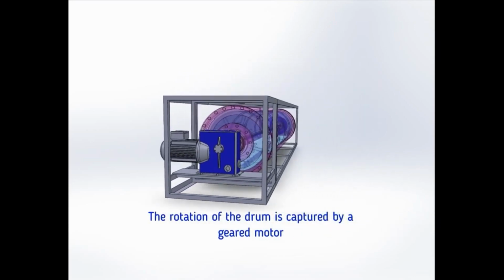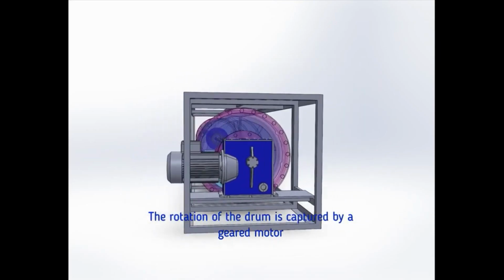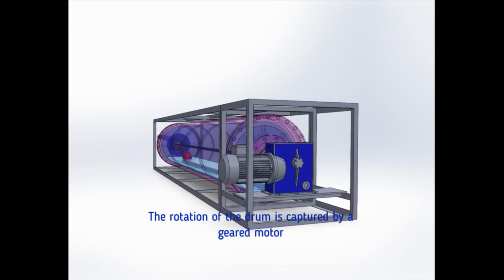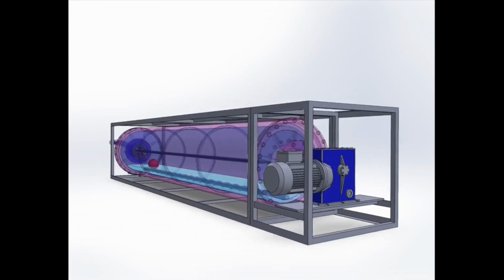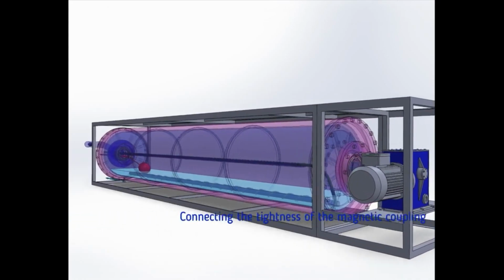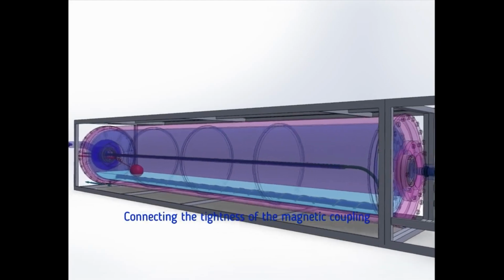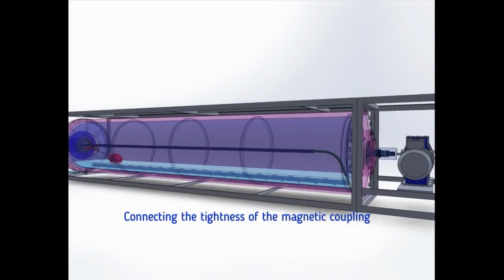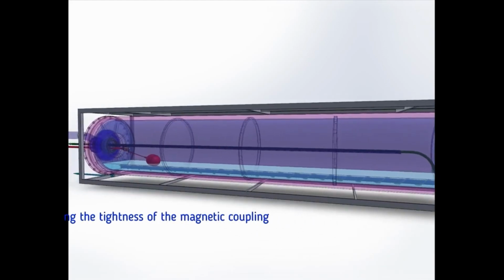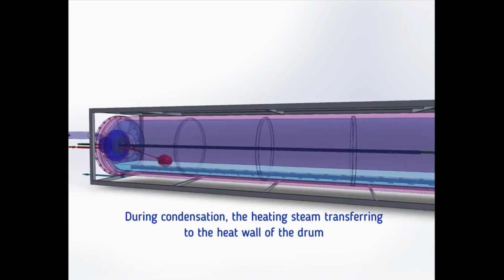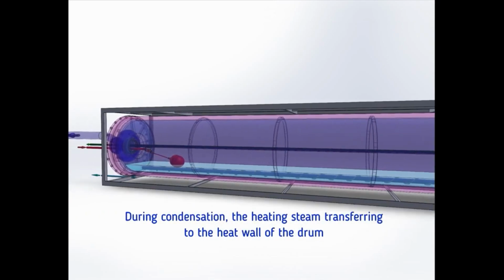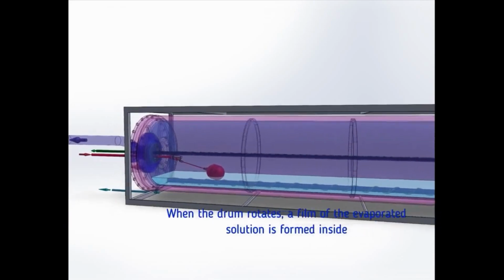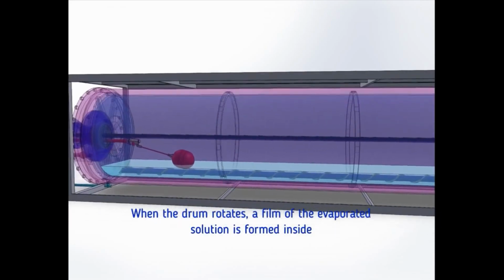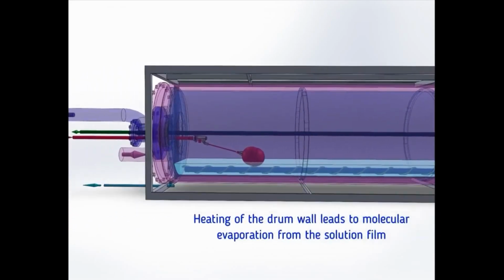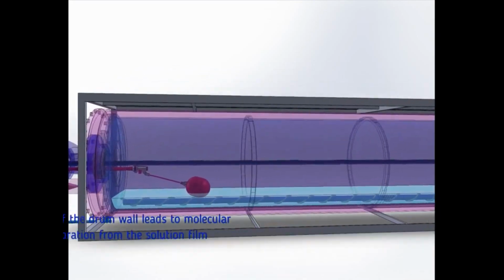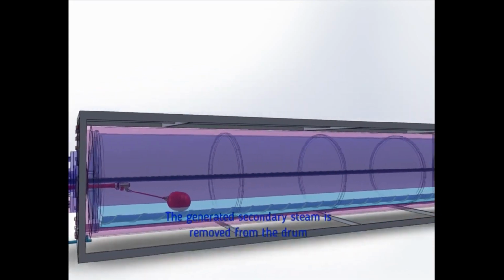The technological process of heat transfer through the wall during evaporation on the inner surface of the drum and condensation on the outer surface, as well as cleaning the inner surface from salt deposits, occur simultaneously. When the drum rotates, which is necessary to create a film of liquid, a spiral wound rod simultaneously rolls under the liquid level in the drum under the influence of gravity. Since it cannot move axially, the spiral coil acts like a screw, moving the resulting salt sediment to the point where the concentrate is discharged from the drum.